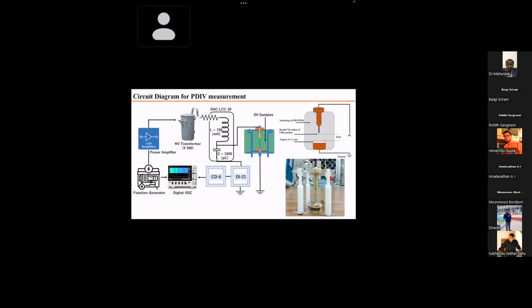This is because of ester oil and palm fatty acid. Palm fatty acid viscosity is somehow close to mineral oil, not very high viscosity, because it is monoester. But in triester oils such as palm fat, your FR3, Jatropha and others, those are triester and they have high thermal conductivity and high heat transfer. But the problem with high heat transfer and thermal conductivity is circulation, and waxing also comes with oxidation. These are three problems added along with these advantages. But thermal conductivity will be higher.